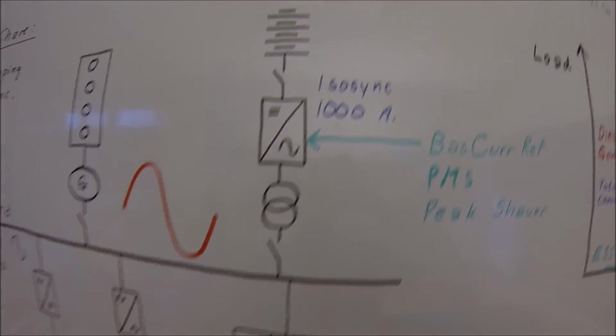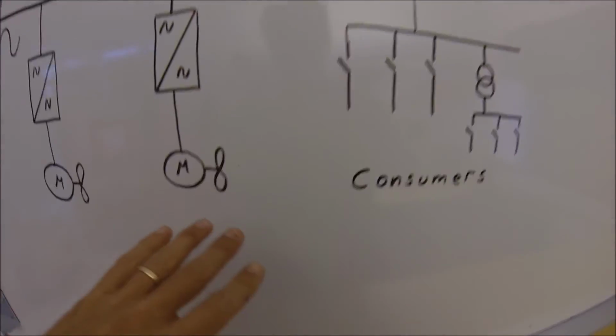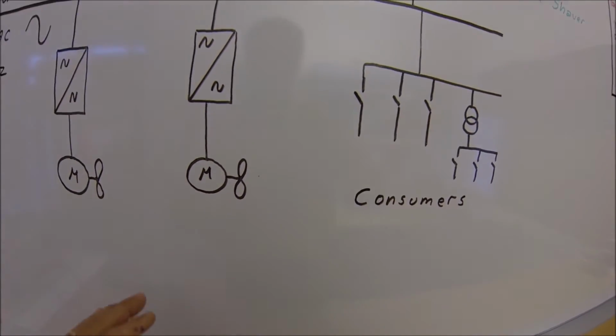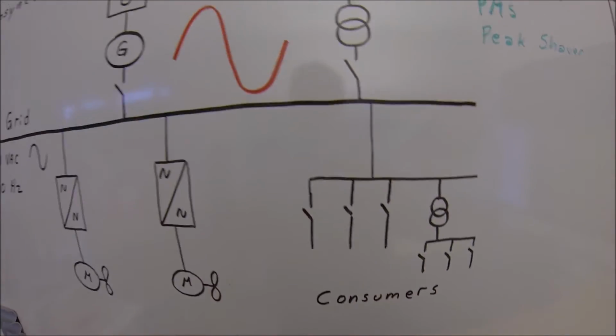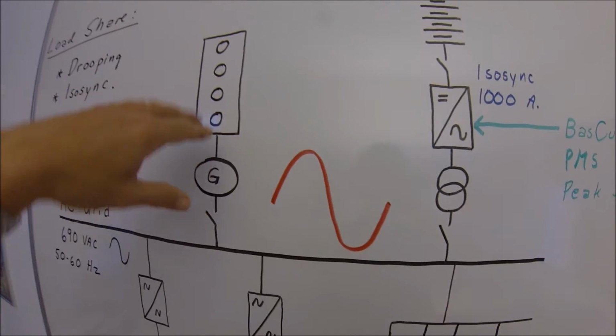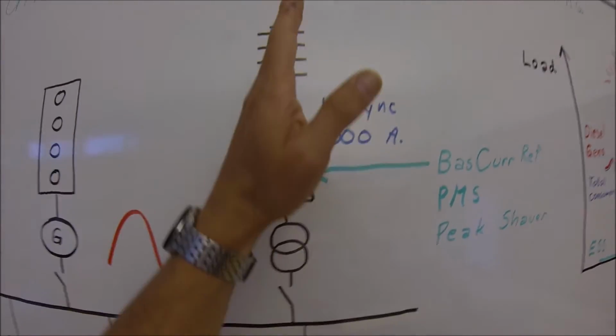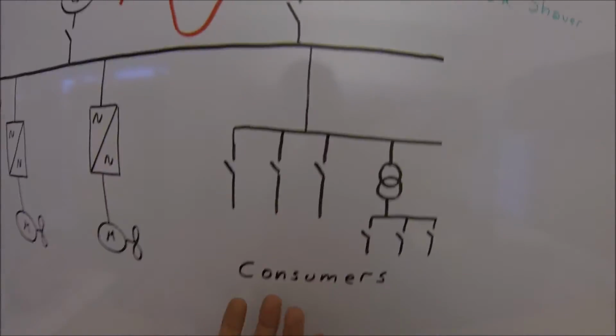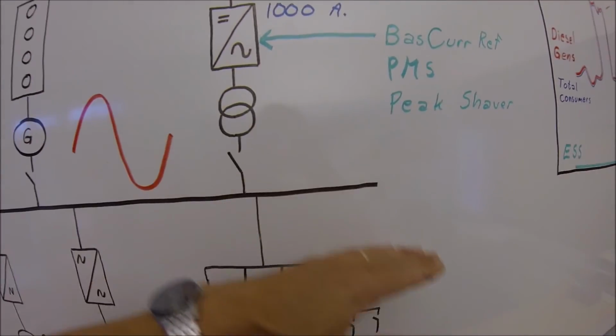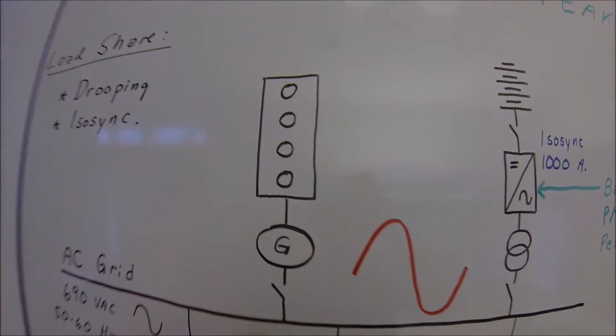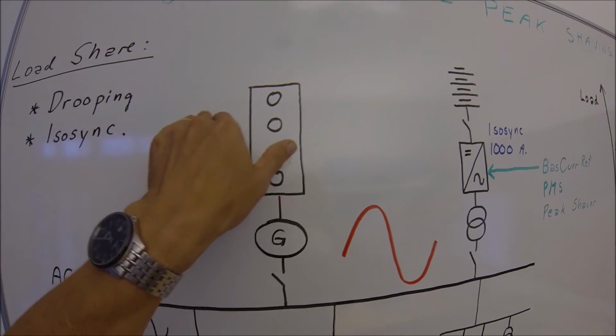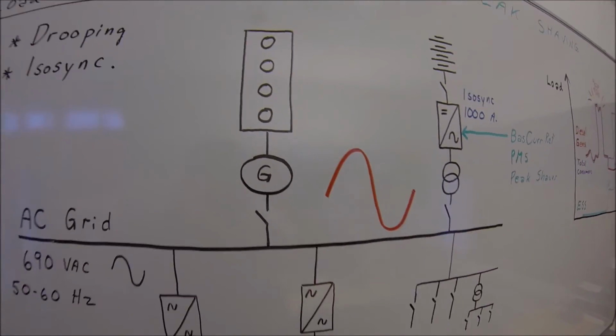So when the thruster here is stopped, suddenly there is no need for all these kilowatts, but you don't want that abrupt change for the generators. So then you can charge the battery just to replace the load that was here, and you can taper it off in a nice way so that your generators see these very nice and soft changes.